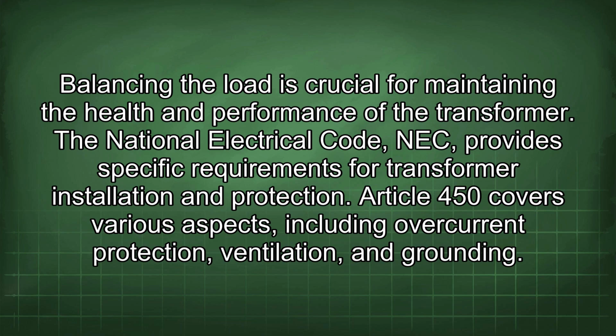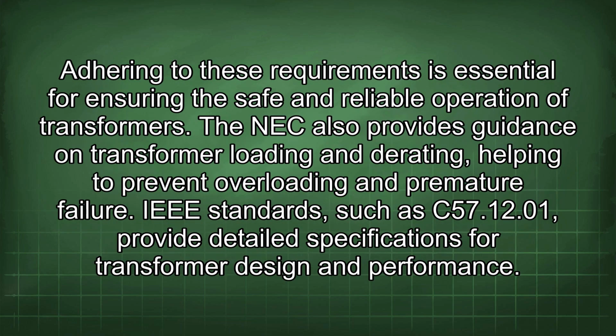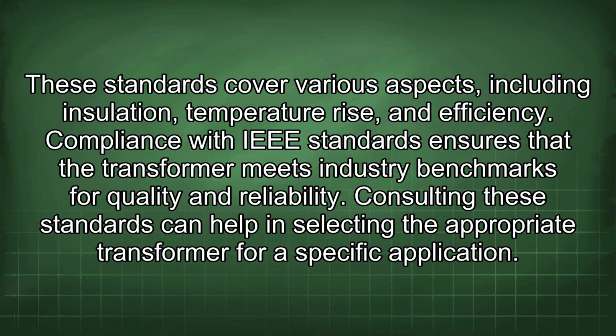The National Electrical Code, NEC, provides specific requirements for transformer installation and protection. Article 450 covers various aspects including overcurrent protection, ventilation, and grounding. Adhering to these requirements is essential for ensuring the safe and reliable operation of transformers. The NEC also provides guidance on transformer loading and derating, helping to prevent overloading and premature failure. IEEE standards such as C57.12.01 provide detailed specifications for transformer design and performance. These standards cover various aspects, including insulation, temperature rise, and efficiency. Compliance with IEEE standards ensures that the transformer meets industry benchmarks for quality and reliability. Consulting these standards can help in selecting the appropriate transformer for a specific application.